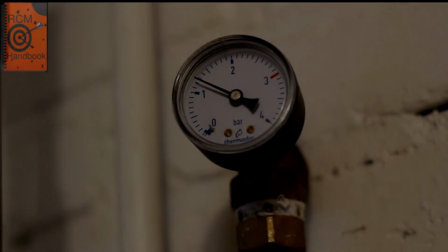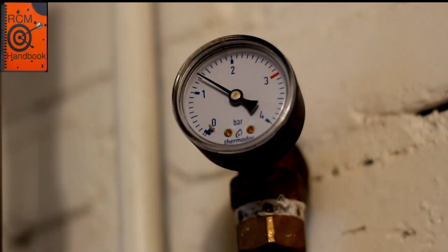The function of this pump in this system is to maintain a pressure of 1 bar. The manufacturer's specification states it can handle up to 2 bar, so this is the asset's capability. But importantly, our function limit is just 1 bar of pressure. If it falls below 1 bar, we have a functional failure.